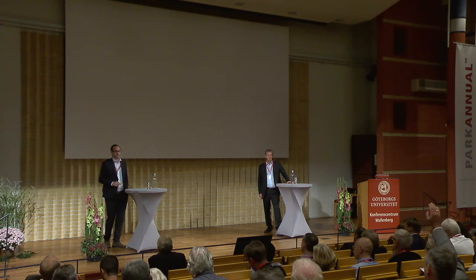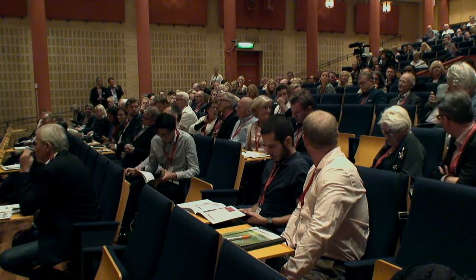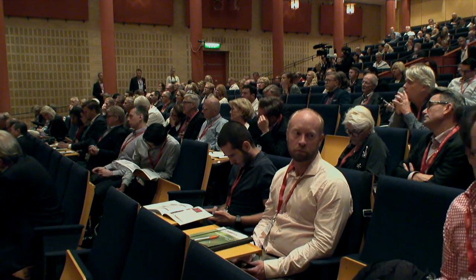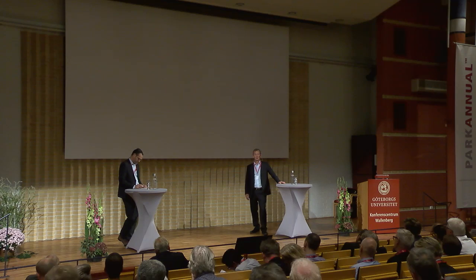Any additional questions? We have one in the middle there. Use the microphone, please. Sorry. Kai Brickman from AstraZeneca. Can you comment on the timescale that you expect to take it from the FDA for the 510K application? Very interesting. They've got this 90-day window, but you can look at the typical times for that product class. There are a lot of NPWT devices out there, and they range from 77 days to 420. So we're hoping to be around 100 days. We've done a pretty thorough job putting together the 510K. It's with them now, but you just never know.